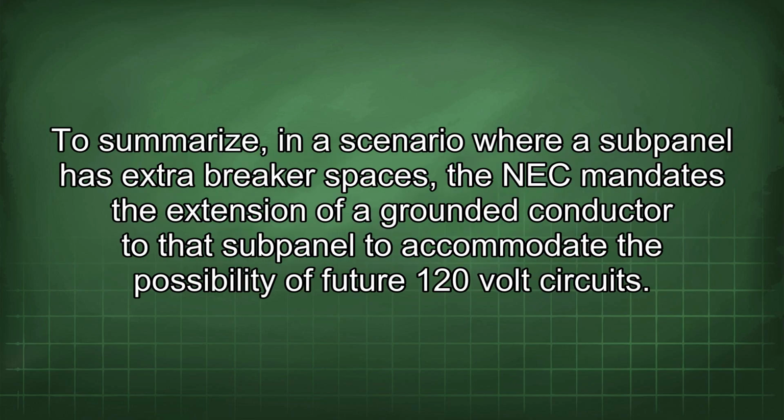To summarize, in a scenario where a subpanel has extra breaker spaces, the NEC mandates the extension of a grounded conductor to the subpanel to accommodate the possibility of future 120-volt circuits.